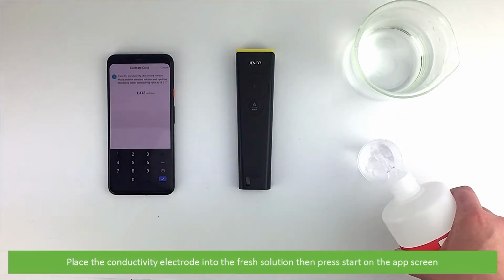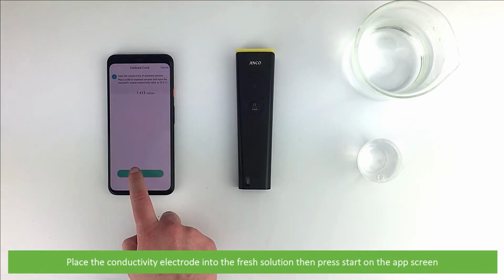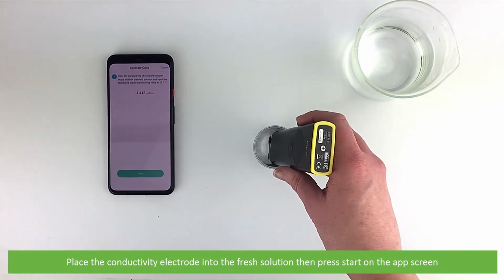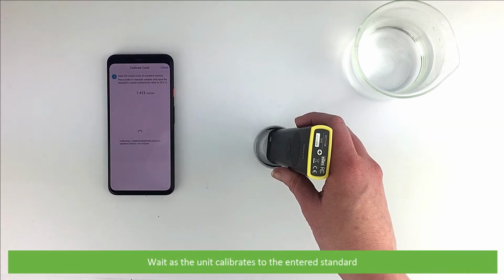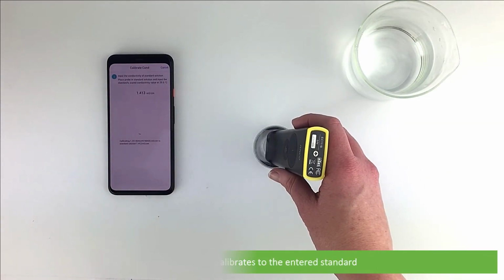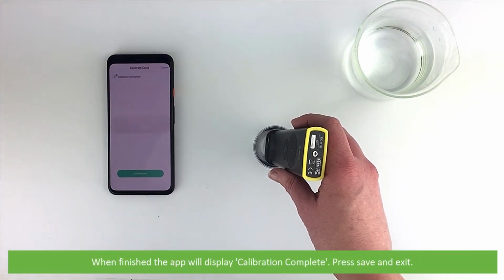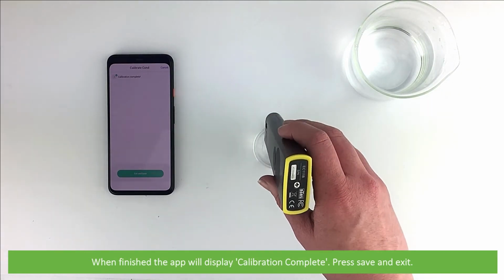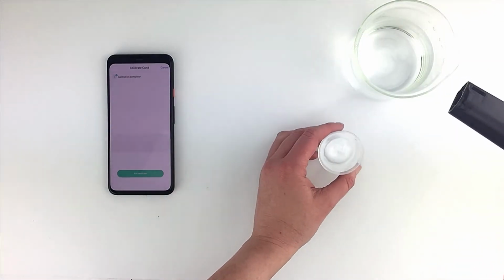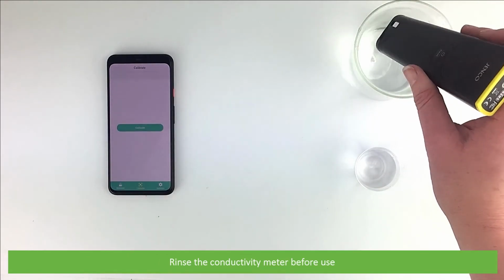Place a conductivity electrode into the fresh solution, then press Start on the app screen. Wait as the unit calibrates to your entered standard. When finished, the app will display calibration complete. Press Save and exit. Rinse the conductivity meter before use.